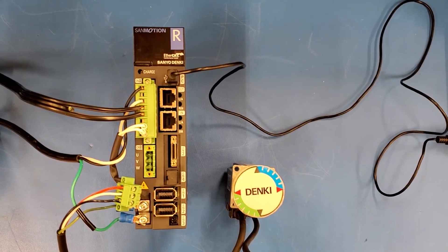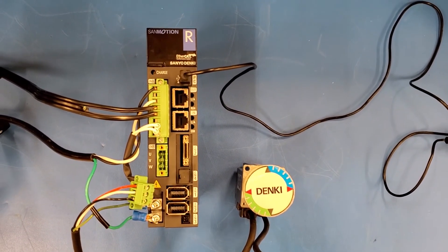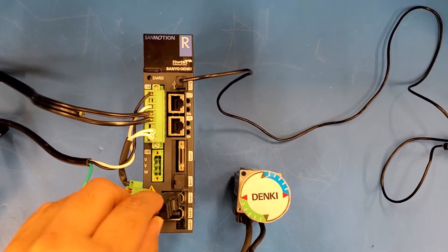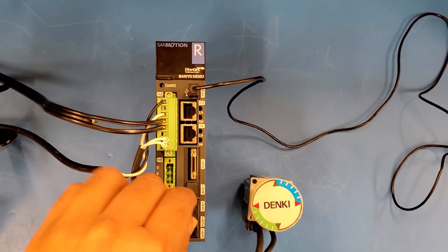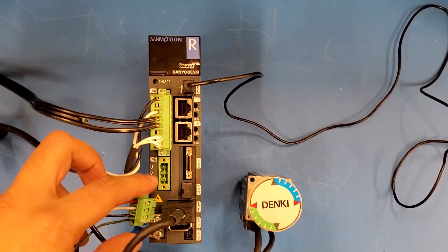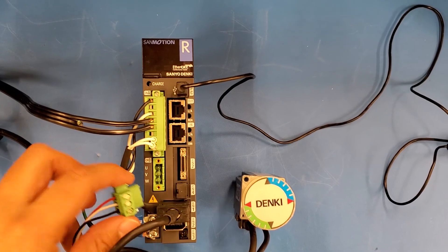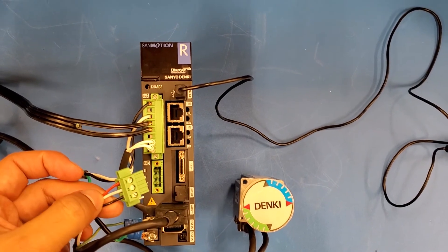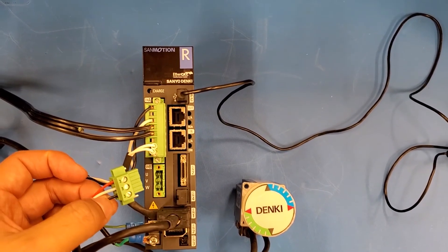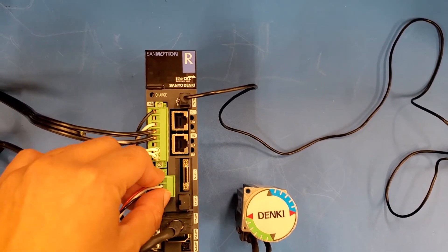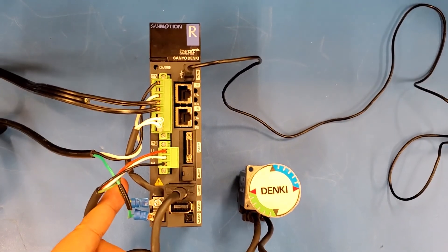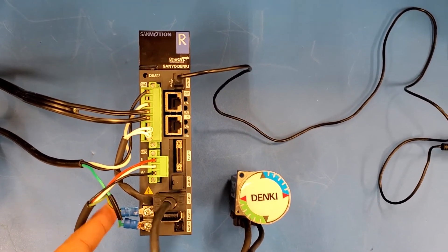Once you have turned off your power, you are ready to connect your motor power cable and motor encoder cable. The motor encoder cable connects to EN1, just like that. Motor power cable UVW: U is for red, V is for white, W is for black. It is connected just like that, and the ground connected to the chassis of the drive.